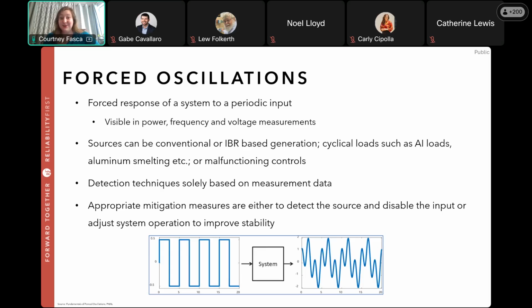You may have noticed that I did skip over the last wave on that graph, the forced response. This gets its own slide to itself. It's a separate category. So when ambient and transient oscillations are called natural responses, forced oscillations fall into their own category of forced response. Creative titling. The forced response is the response of the system associated with an external input, a rogue input. This could be something like malfunctioning equipment, unintentional behavior stemming from control systems that need to have been better coordinated, and it can come from any generation type, IBRs and conventional generation included. It can even come from a poorly tuned PSS.